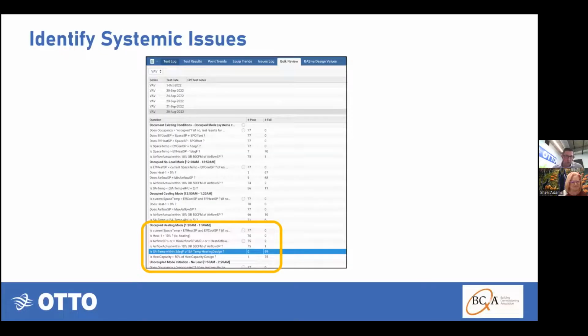We have a tool we call bulk review, where you can look at each functional question and see how many boxes got good answers versus bad answers. In this example, out of 75 boxes, 69 had heat coils, and 6 were cooling only. For the ones with heating, we asked a simple question: is the supply temperature within a few degrees of its design discharge temperature from the approved control submittal or mechanical schedules? The answer was no across the board.